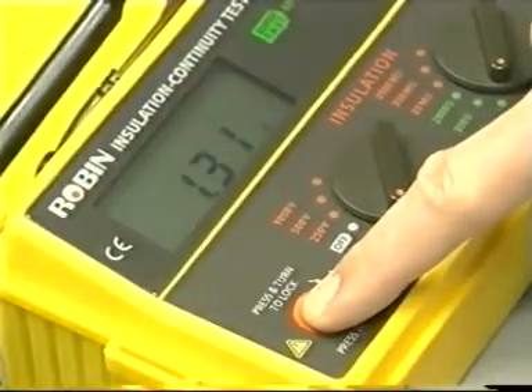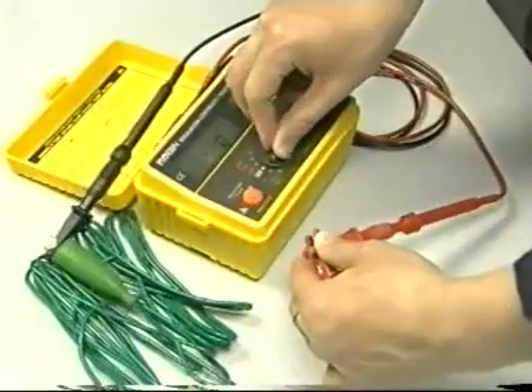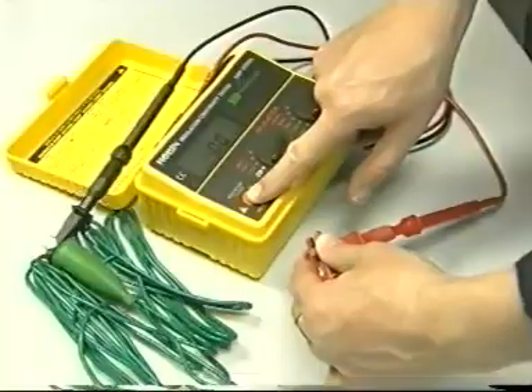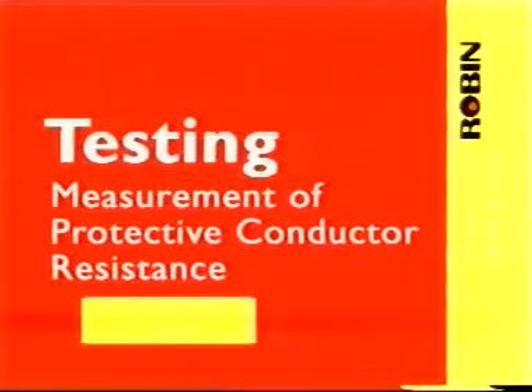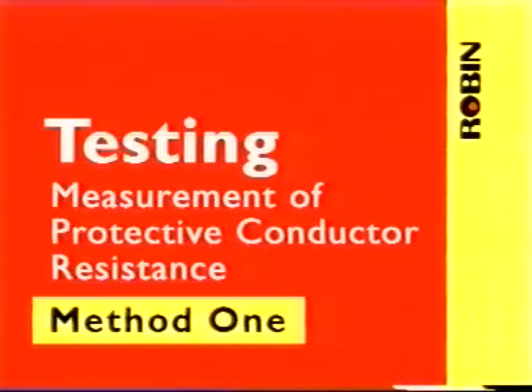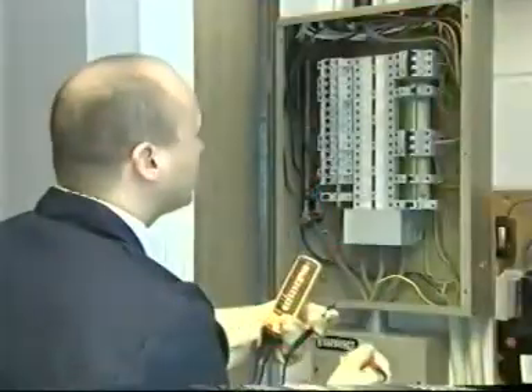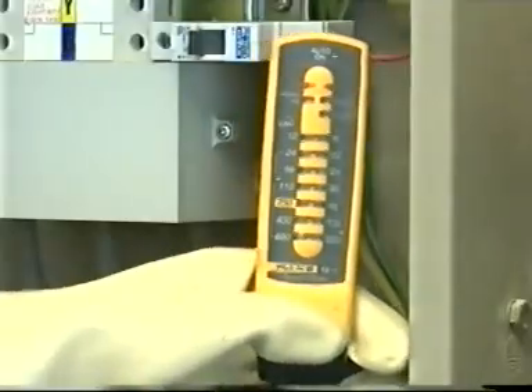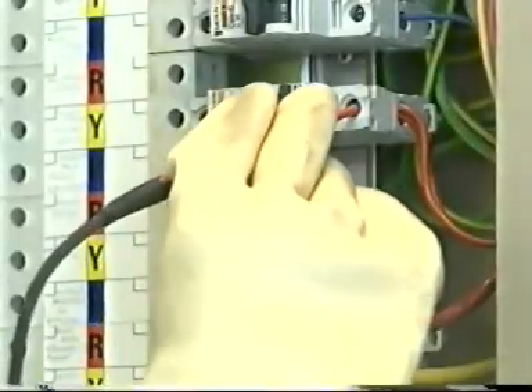Continuity tests are for the purpose of verifying that protective conductors are sound and correctly connected. There are two suggested methods of measurement. Method 1 is probably the most common. First, prove the conductors to be tested are isolated from all live or charged sources of energy.